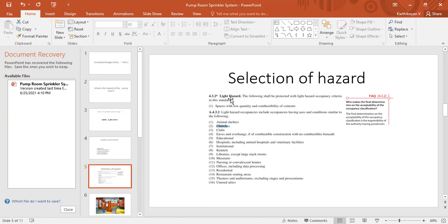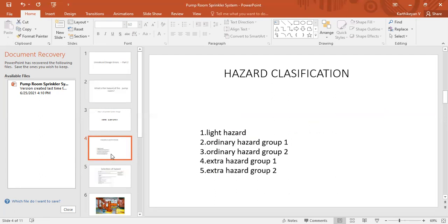They have listed out some examples. You can see here, listed out the NFPA light hazard occupancies like museum, churches. It contains some less amount of combustibles, so they have listed it under the light hazards. So what are all the hazard types? Light hazard, there are three types majorly: light hazard, ordinary hazard, and extra hazard. Ordinary and extra hazard contain two groups, group one and group two. This is the basic introduction of classifications of hazards.